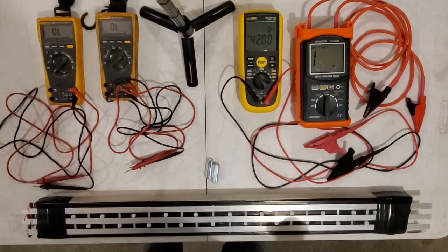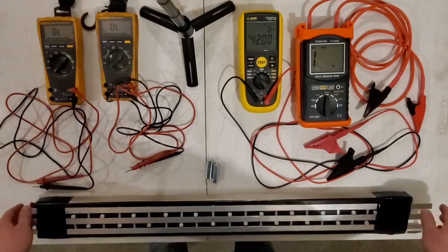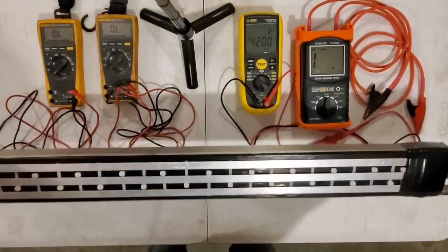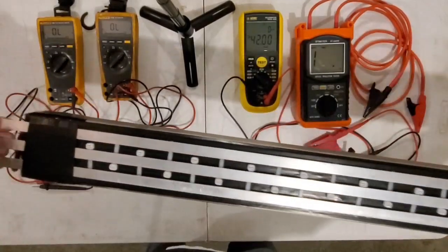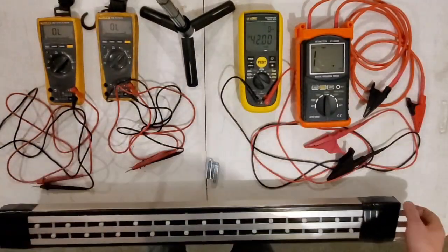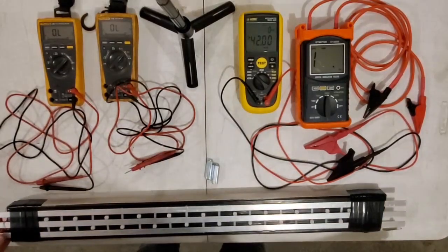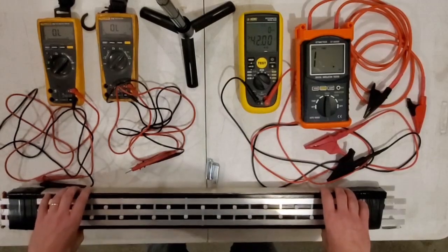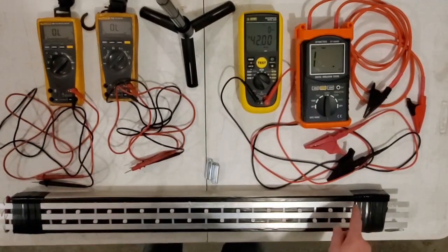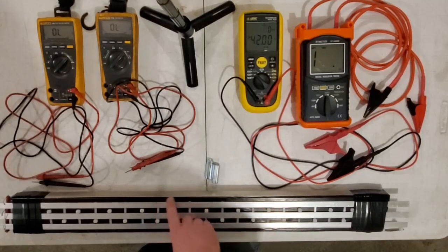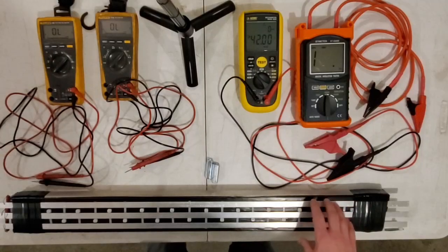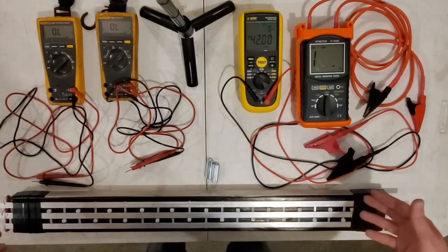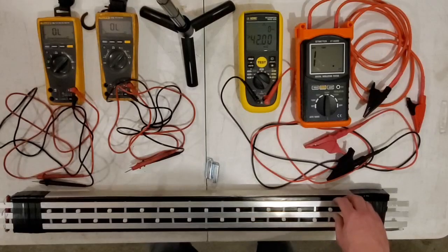So insulation resistance is essentially a simulated bus that I've created. You've got three-phase conductors and you've got a grounded frame behind it, okay? So it's just a lot of electrical tape, some aluminum, and some shielding, all right? And so what I want to talk about is if you're going to use electricity, you want to make sure that the electricity and the charges flow only where you want them to. You don't want them going to other things because we could be standing there, working there, right? So what we want to make sure of is that the electricity stays where we want it to. And that is our insulation resistance.